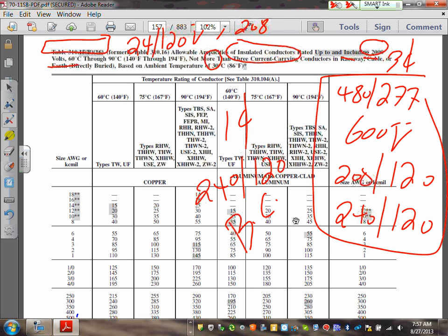How about the feeders? Oh, before I forget, how about branch circuits also, feeders and service conductors larger than 400. I forgot to mention, do you remember the last table has a limitation, how high you can go in the last table, 400. Now what happens if your apartment building is 800 amp? Switch to this table. Did you guys hear me?